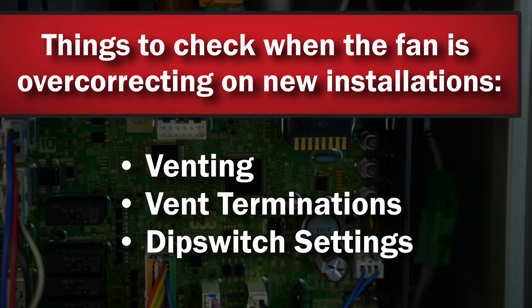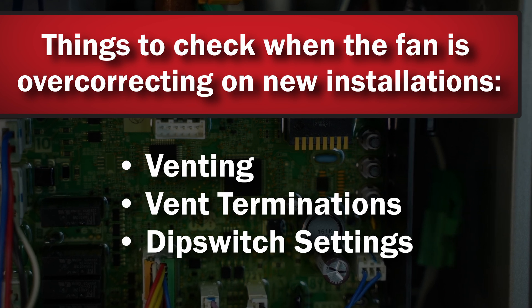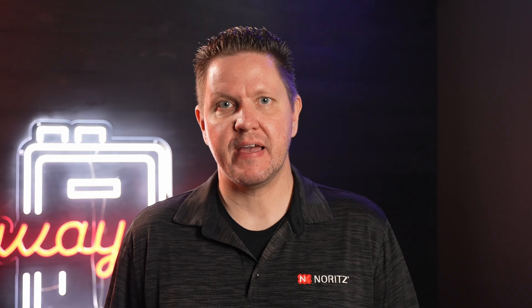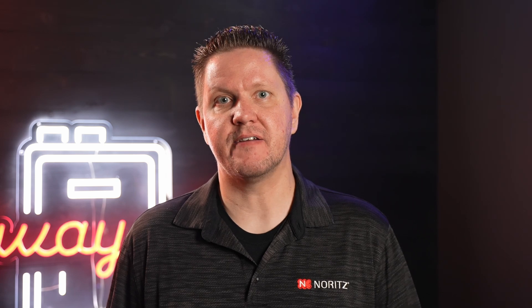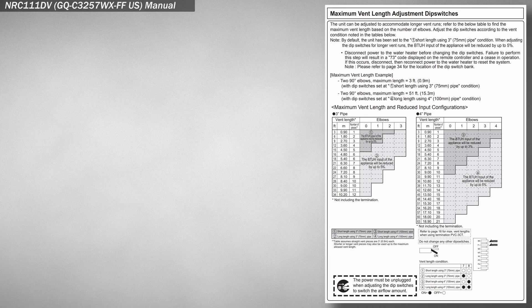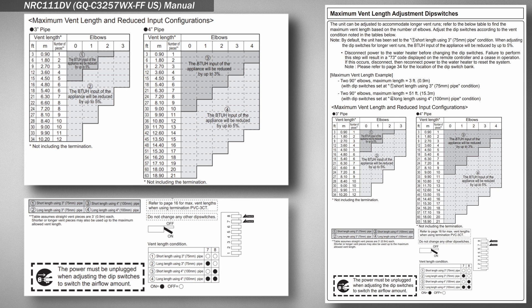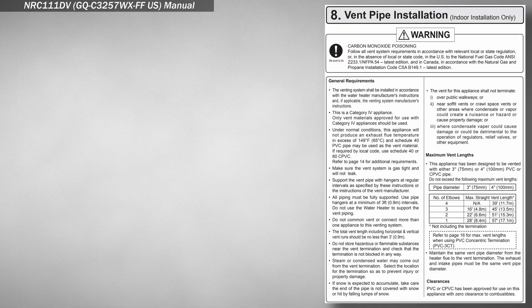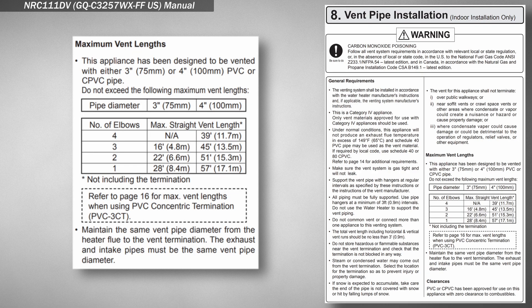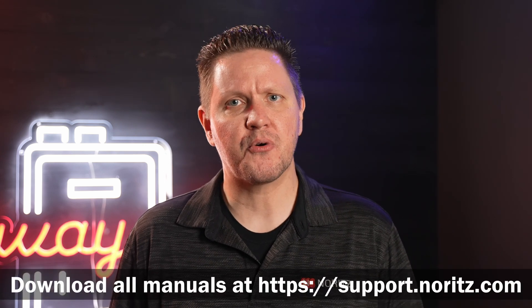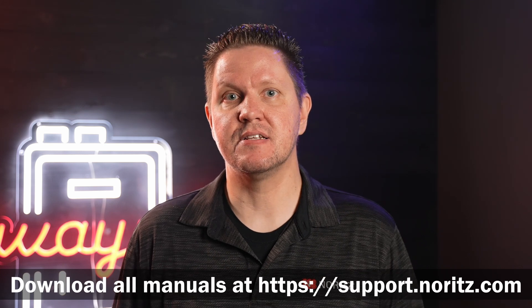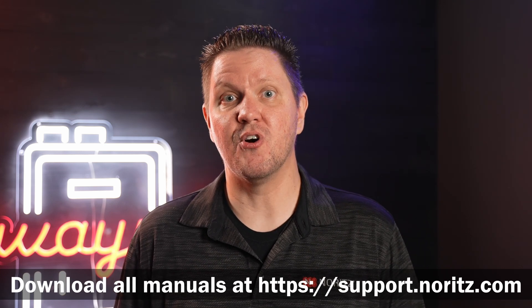For new installations that show the fan is overcorrecting, you'd want to check all things related to the venting, termination, and dip switch settings. An overcorrecting fan is the heater's way of telling you it can't breathe properly, so you need to check all aspects that affect the unit's ability to pull in fresh air or remove the exhaust. Depending on the size, length, and number of elbows used in the venting, certain dip switches in the unit will need to be turned on. Make sure that the size and length of venting used falls within the acceptable lengths allowed in the installation manual. There is no combination of dip switch settings that can correct for a vent that is too small a diameter, too long, or has too many elbows. That's why it's incredibly important to read the manual before installation so you are aware of everything needed to perform a correct installation.